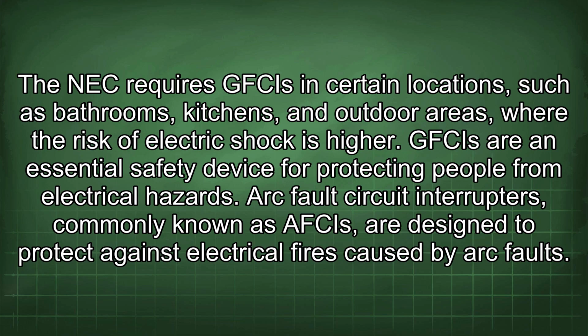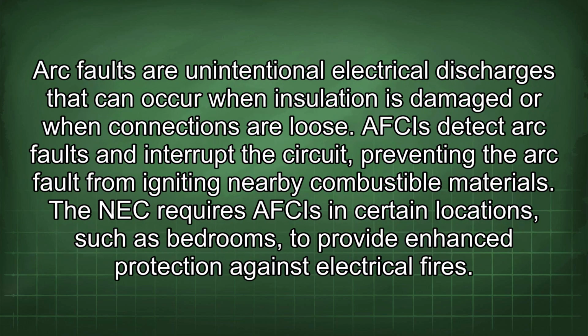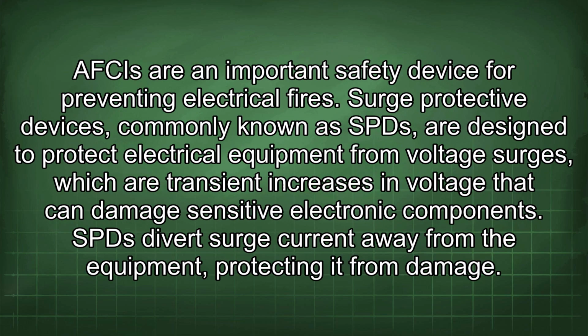Arc fault circuit interrupters, commonly known as AFCIs, are designed to protect against electrical fires caused by arc faults. Arc faults are unintentional electrical discharges that can occur when insulation is damaged or when connections are loose. AFCIs detect arc faults and interrupt the circuit, preventing the arc fault from igniting nearby combustible materials. The NEC requires AFCIs in certain locations, such as bedrooms, to provide enhanced protection against electrical fires. AFCIs are an important safety device for preventing electrical fires.